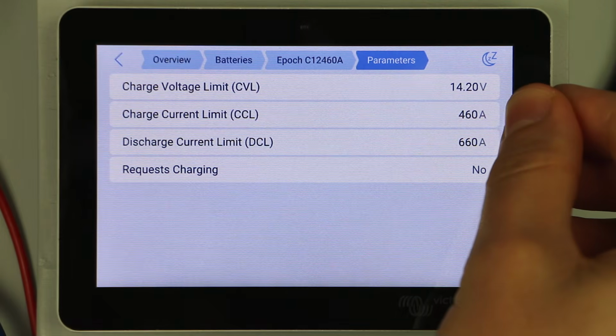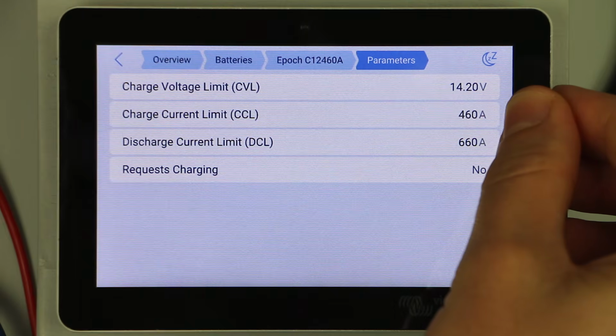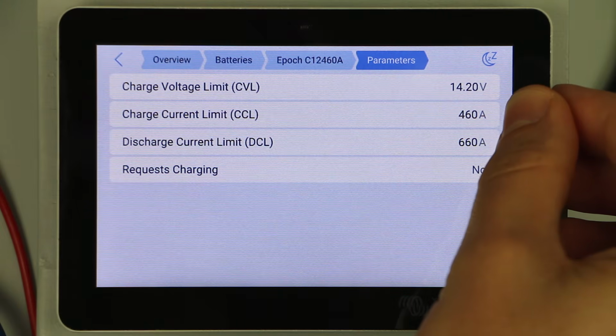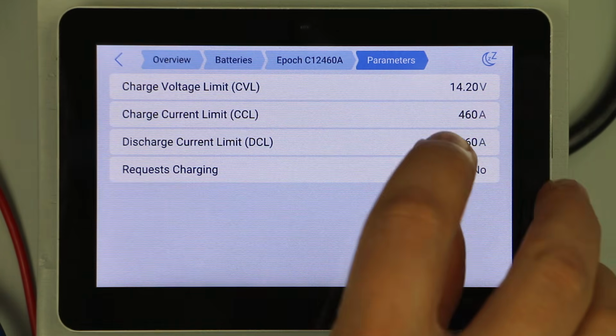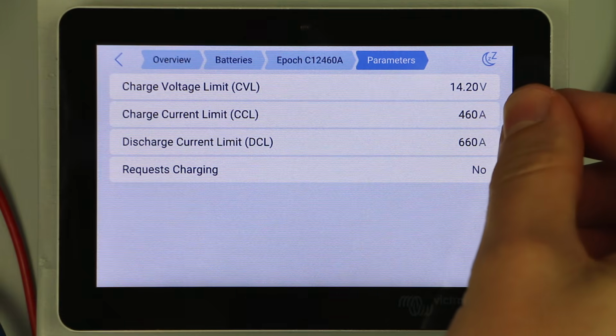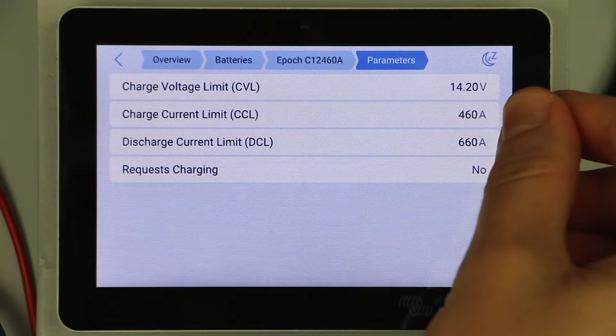Next up, we have our charge current limit. This is based on 230 amps per battery for the 12 volt Epoch Elite model. This number is not going to change very often. Occasionally, if you are charging the batteries and one of the cells gets too high on its voltage, it will remove itself from charging, and you'll see this number drop by 230 amps to indicate that that battery has dropped out and it no longer wants a charge.